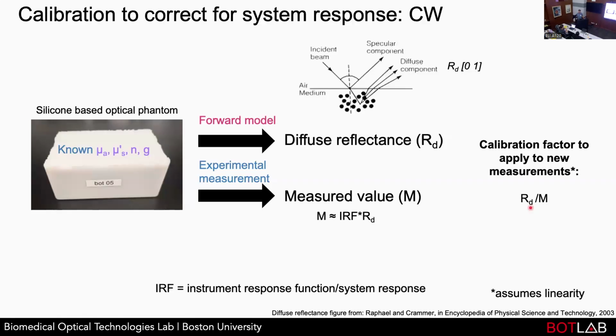This is an interesting one that people have studied. If you calculate your calibration factor today, can you use it tomorrow? What we use in practice in academia, in my lab, is that before we take a measurement on a patient, we do another calibration measurement. After we take a measurement on a patient, we'll do the calibration measurement again and just see if those calibration factors change.